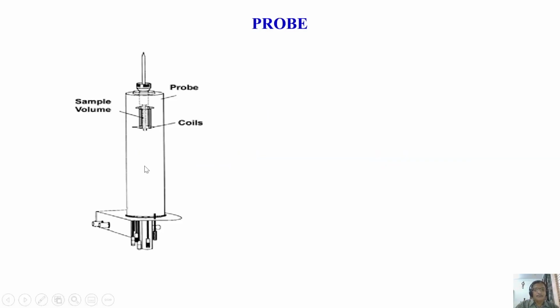The probe is like this. See, inside we have simply a coil here. When you put the sample here, the tube goes and sits inside this RF coil. Okay, the sample sits here. Now, when we go through the transmitter to the console, you generate the radio frequency pulse, and you send the pulse. This coil is the one which ensures the spins inside this NMR tube get excited.